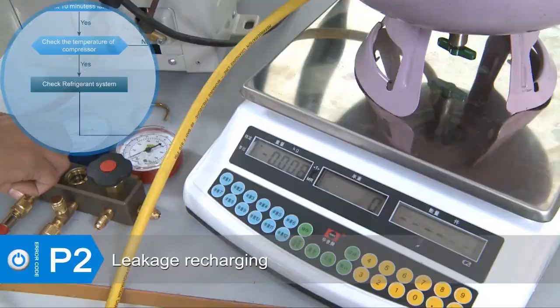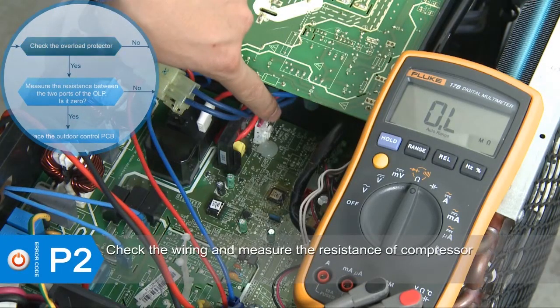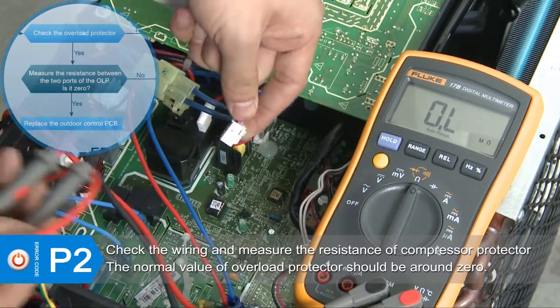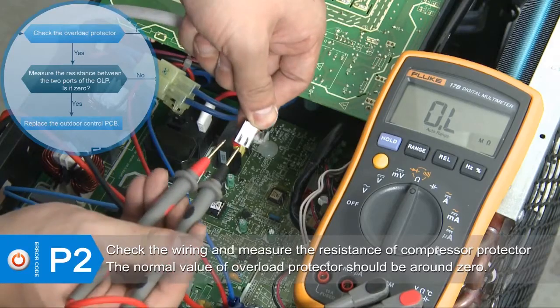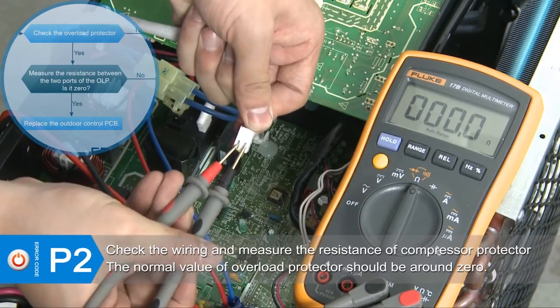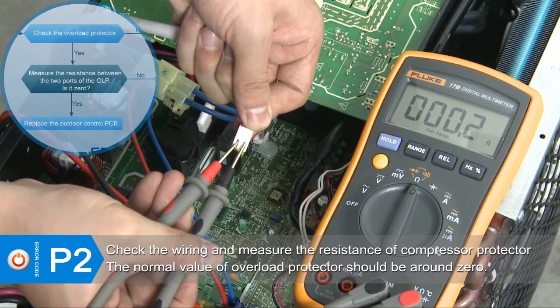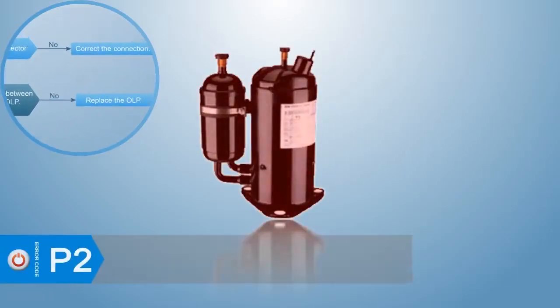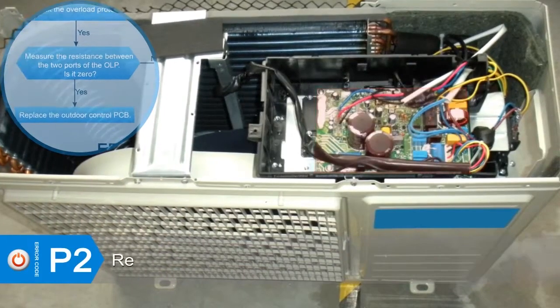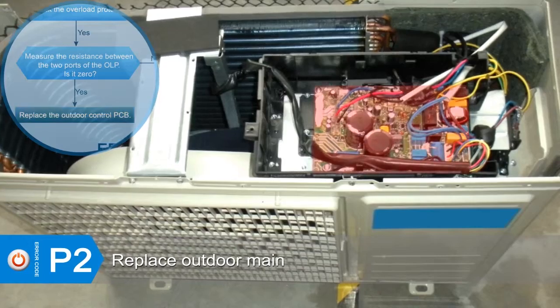If the refrigeration system is blocked, replace the high-pressure valve. If the temperature of the compressor top is higher than 100 degrees Celsius, check if the wiring of the overload protector is well connected. If the wiring is good, check the resistance value of the two ports of the overload protector — the normal value should be around zero; otherwise, replace the overload protector. If the error still exists, replace the outdoor main PCB.